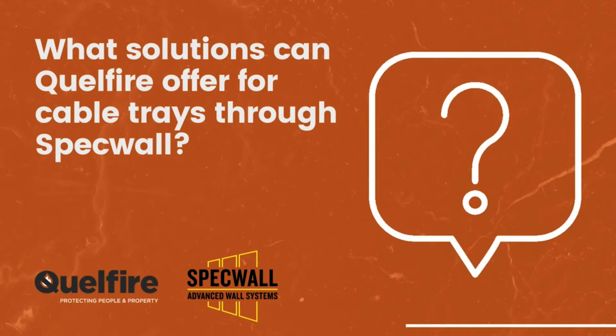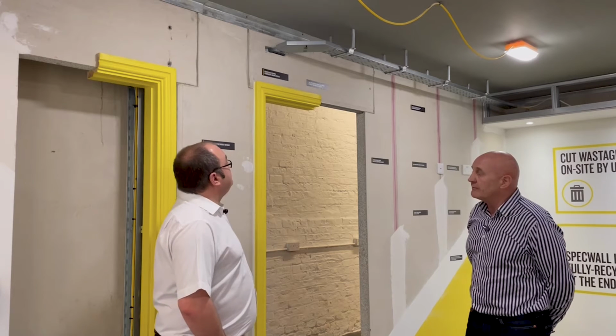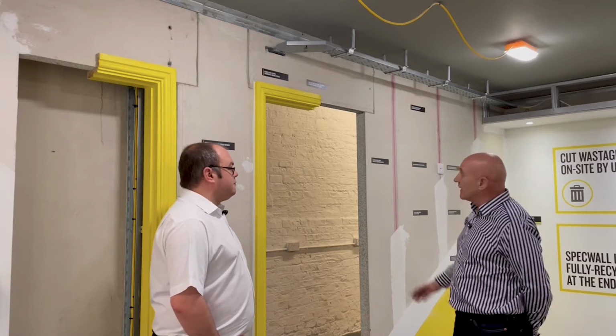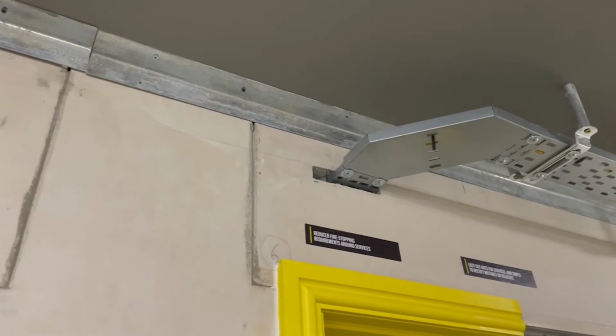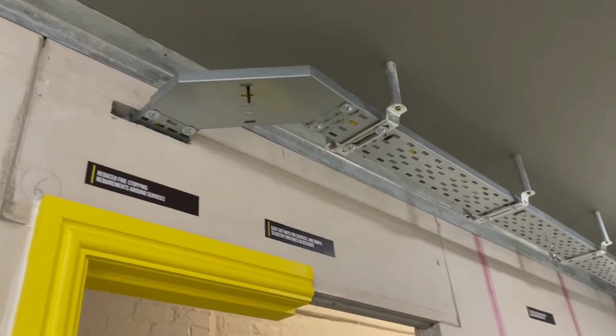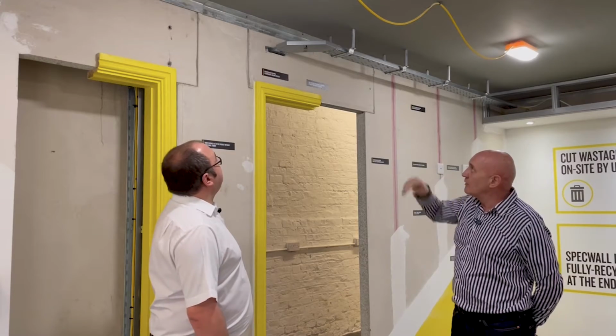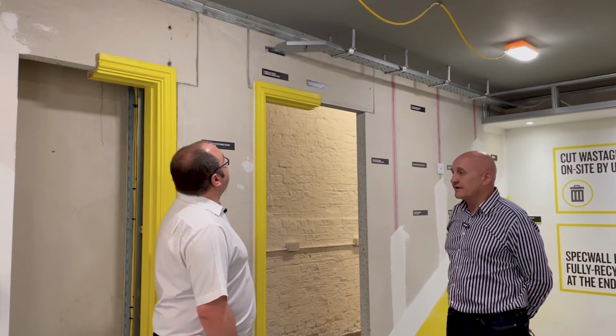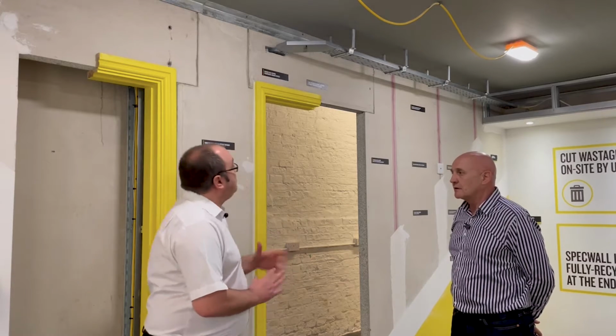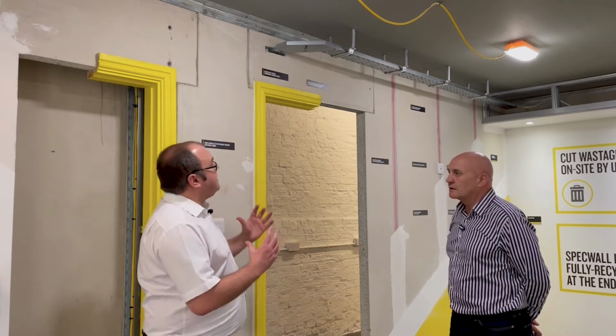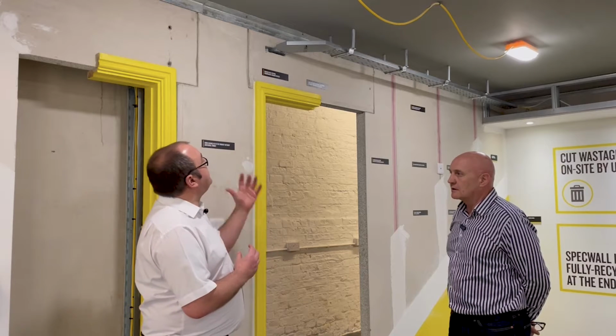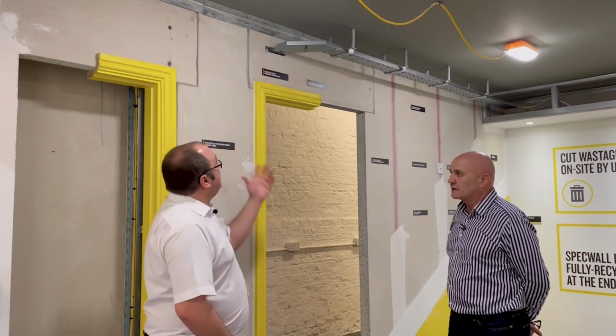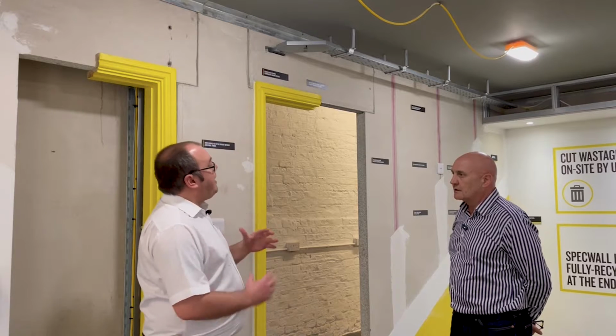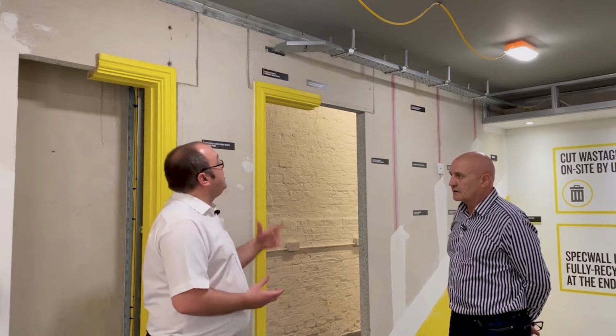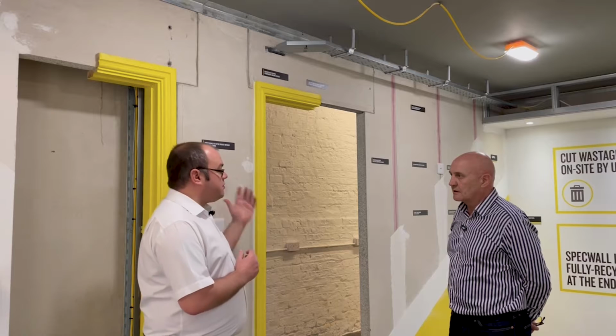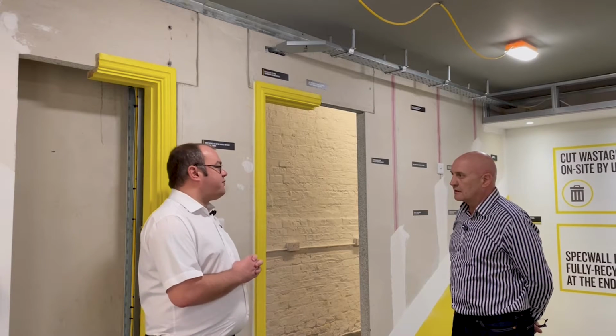What we're finding, Alec, is that the M&E lads are really warming to the fact that they can bring the trays along, find a position they want to penetrate through the wall, and it can be cut in position. How can we provide a tested solution to fire stopping that? Great question. With that sort of application, because typically you'll have an oversized hole around your tray as it's the easiest way to feed it through, we would look to use our Quelstop Fireback Pattress system, which we've fire tested and achieved the necessary results to retain that fire resistant performance.